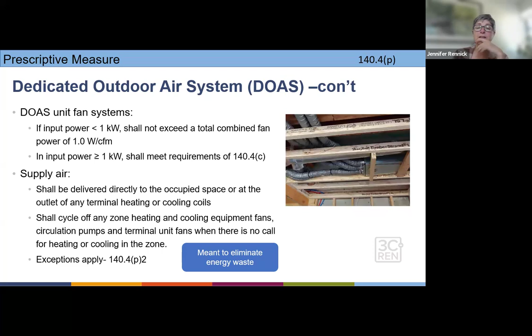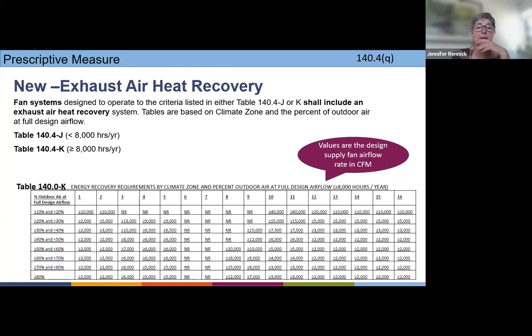And so for the code, to give you an idea, and again, this maybe is more applicable to the mechanical engineers, there are now prescriptive measures talking about the energy recovery requirements by climate zone and by the percent outside air. And so sure, you can look it up by table. I think it's great because it gives us a window into what is going on with how these measures are being set up. But a lot of the mechanical engineers and a lot of the folks we're working with, they're putting this into the computer program, letting it crunch, and we're getting an answer that says, yep, it passes or it doesn't pass. I'm not going to pretend to be the engineer on this. But this gives you an idea of what those values are now, and those are new.